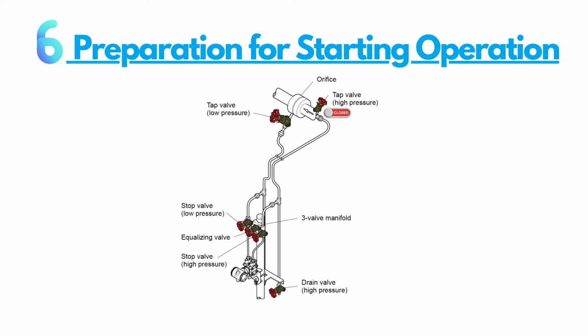Step 6. Preparation for starting operation. Check that the process pressure tap valves, drain valves, and 3-valve manifold stop valves on both low pressure and high pressure sides are closed, and that the 3-valve manifold equalizing valve is opened. Open the low pressure and high pressure tap valves to fill the impulse piping with process liquid. Slowly open the high pressure stop valve to fill the transmitter pressure detector section with process liquid. Close the high pressure stop valve. Gradually open the low pressure stop valve and completely fill the transmitter pressure detector section with process liquid. Close the low pressure stop valve. Gradually open the high pressure stop valve. At this time, equal pressure is applied to the low and high pressure sides of the transmitter. Check that there are no liquid leaks in the impulse piping, 3-valve manifold, transmitter, or other components.